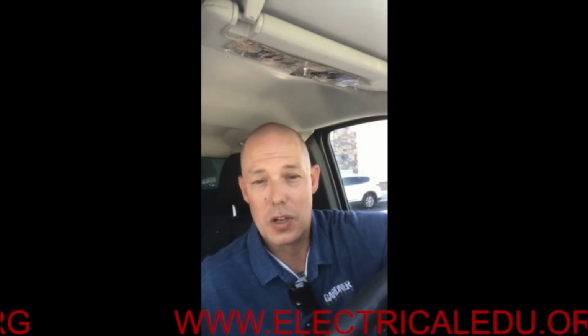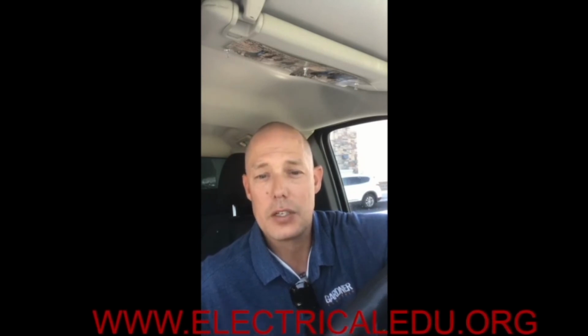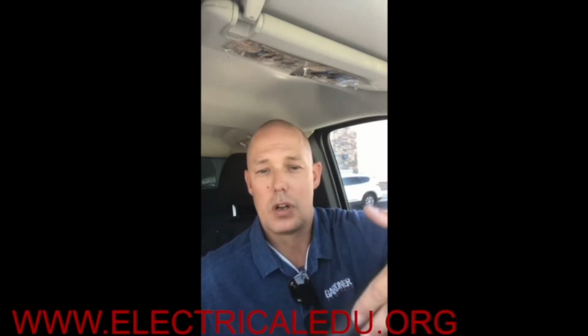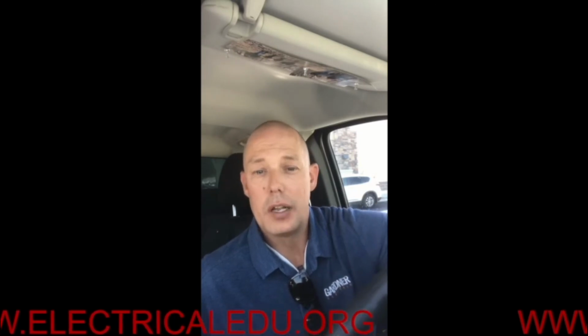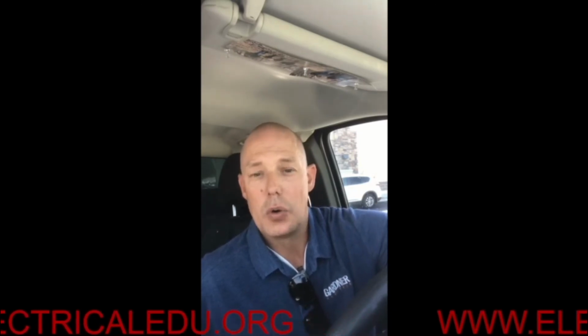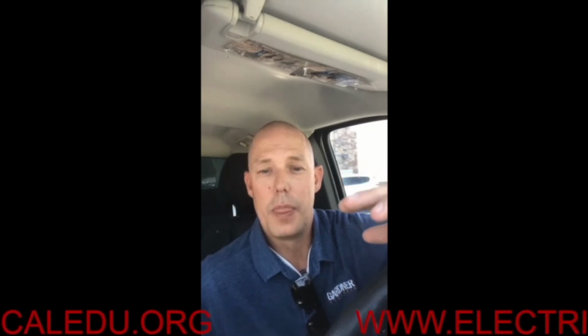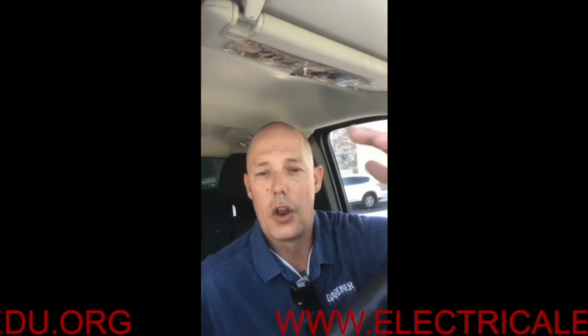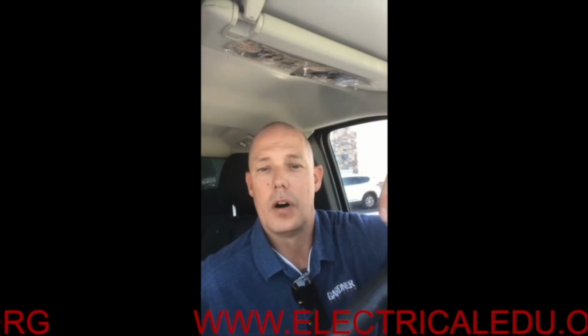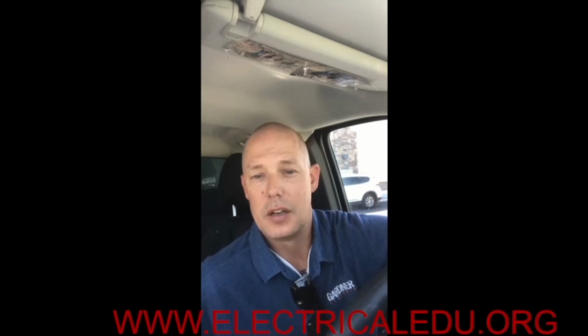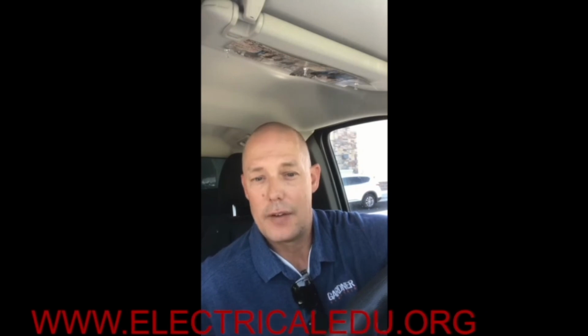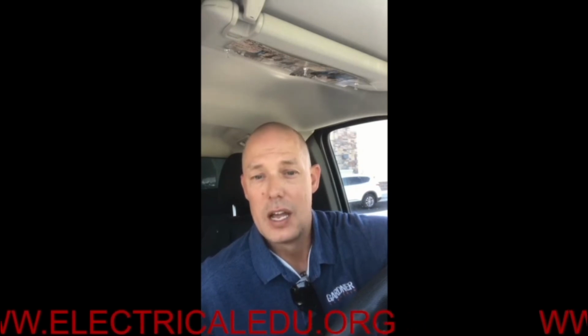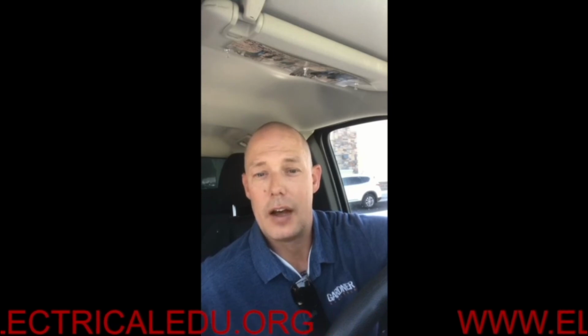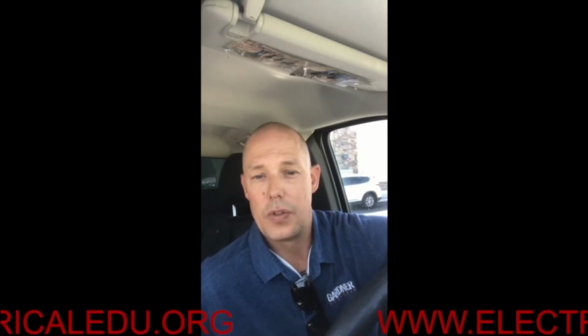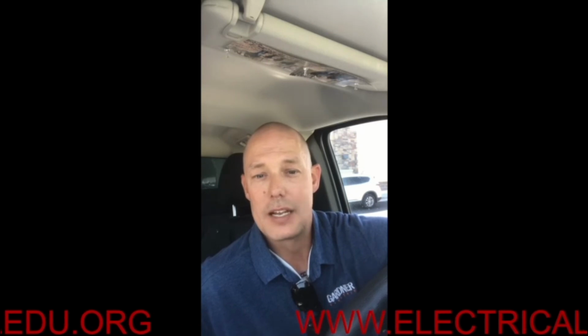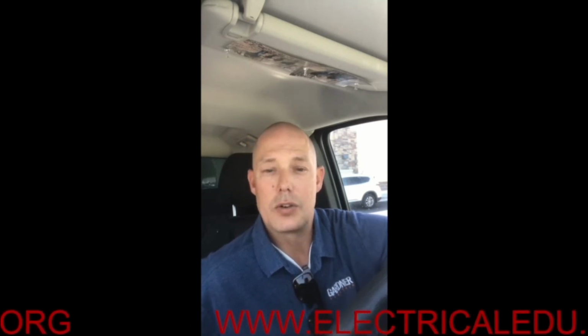So it doesn't make sense to a lot of guys that just size things off of the breaker size, which, I mean, you could do, but over a long period of time, you could be saving money on downsizing wire. So this is one instance where you would size the wire not off the overcurrent protection, but off of the minimum ampacity that is allowed on the nameplate. And then you could have the maximum overcurrent protection device at 45 amps. That's what you have to have. Have that breaker, 45 amps, with a number 10 wire on it. And that's how you size wire for a condenser unit for air conditioning.